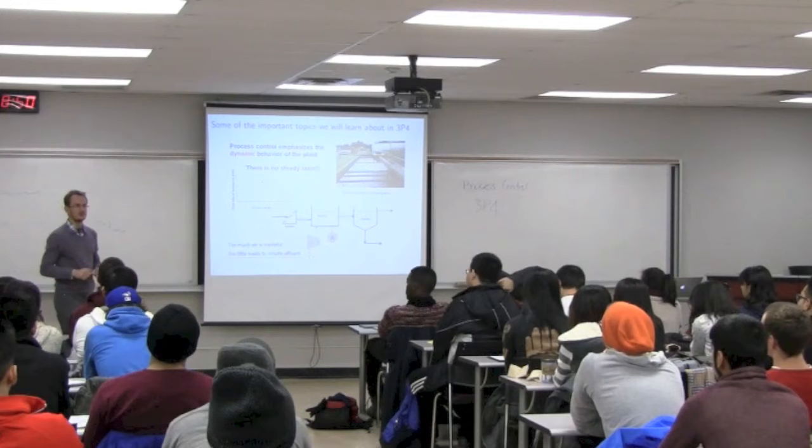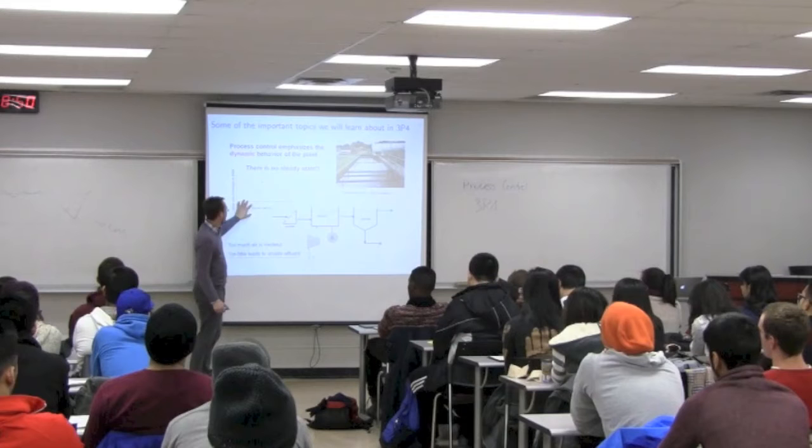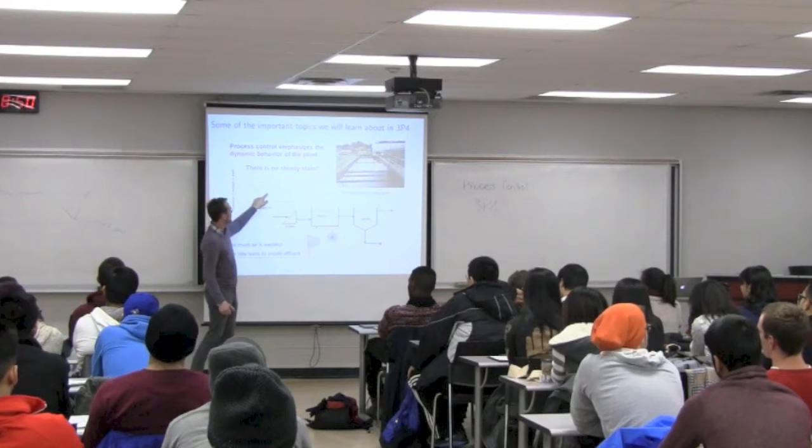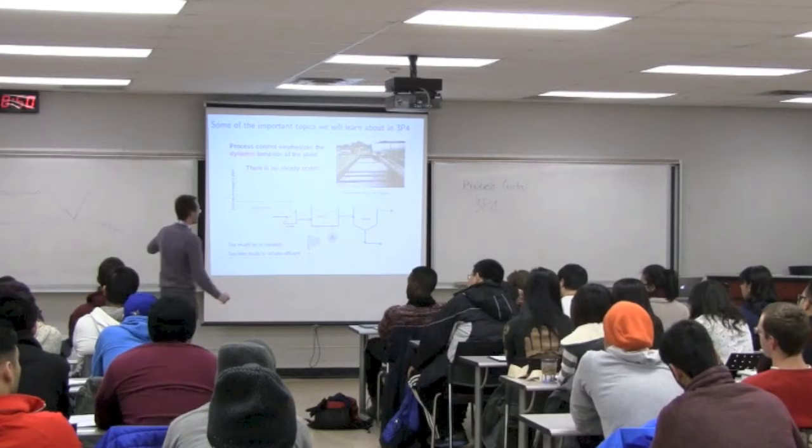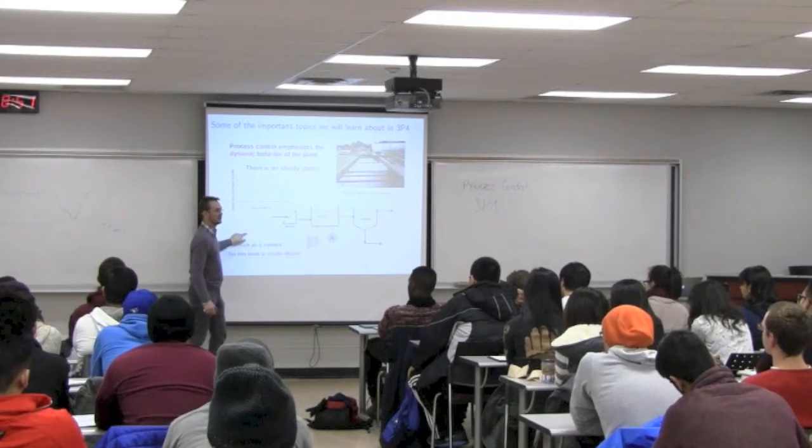A large initial reservoir. Absolutely. So any wastewater treatment company has a large vessel size over here, where this wastewater flow of varying flow goes into that treatment vessel, and they rather let the vessel level go up and down, and then the flow rate out of the vessel is pretty constant. So the flow rate going into the rest of the process is constant. But if you draw a vessel up here in the front, the level in that vessel will be fluctuating. So that's one way to do it.